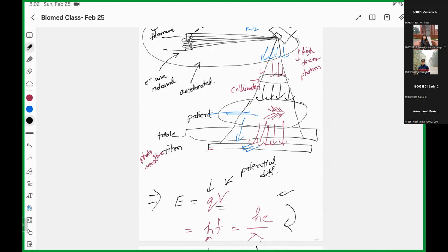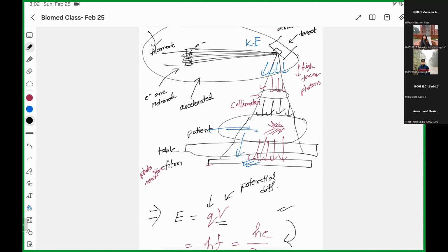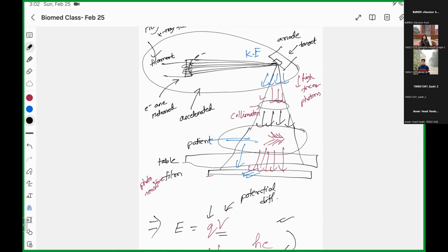The high frequency photons that pass through, the aluminum plate we put will not reduce them much. It will be enough to reduce the soft, small energy photons, but the high energy photons will actually penetrate. It might reduce those insignificantly. Whatever it reduces is insignificant. We'll still get this visual spectrum. The visualization we want, it will be enough to actually do it.